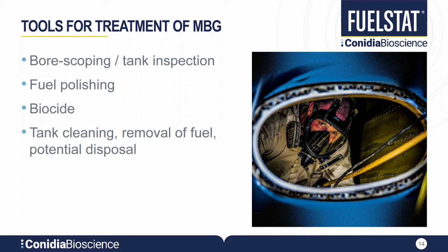Having highlighted that not all organisms will degrade fuel, why would you want to act upon a result that may have been influenced by outside sources, such as whether an operative may not have washed their hands, or that the sample was left unsealed and exposed to the environment? Having a look inside the tank for signs of contamination would be a logical and fairly cost-effective place to start, potentially saving money in remedial action or downtime. Looking into the tank will help identify the extent of the problem.